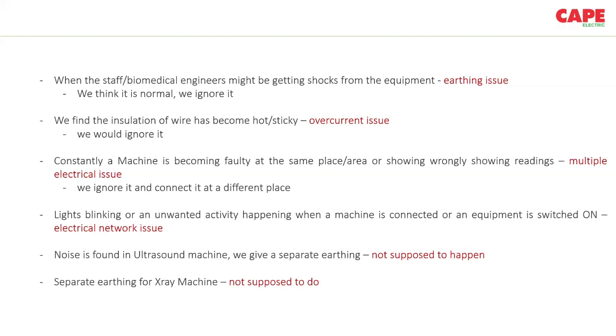We'll just ignore it or connect it to a different place and check. That is not the reason. It is an electrical issue. And especially in case of an X-ray machine, the common thing is that when we buy an X-ray machine, the company people will advise us to put a different or separate earthing other than the hospital earthing. We are not supposed to do that. If we do it, there will be a potential difference actually between the earth of the X-ray machine and the hospital earthing. So all of these things are some common problems that can lead to an electrical hazard at some point in the future. Not right now. It might lead into an electrical hazard at some point.